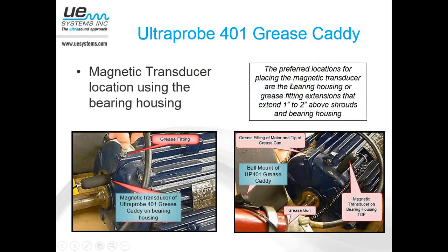Now, we prefer to make contact directly to the motor housing itself or the bearing housing. Again, closer to the bearing is going to be more ideal. So you can see here in this picture, we're just simply making contact, again, close to the bearing housing there. I've also seen people, if they have the grease fitting extensions that extend up just a couple of inches above the motor housing, simply pop the magnet on the side of that grease fitting. You have to think, that grease tube acts as a waveguide, so that sound has a much easier means of travel via that grease tube. Plus, if you're using the grease fitting, again, it makes it more repeatable. We're testing in the same location every single time.